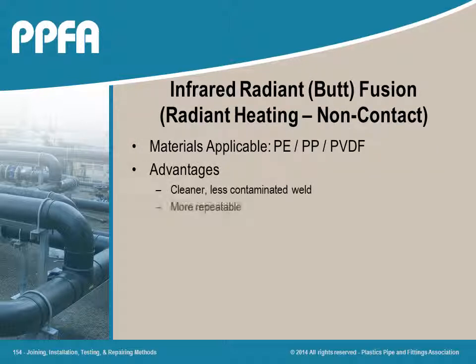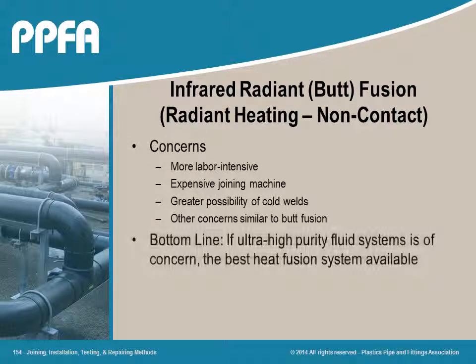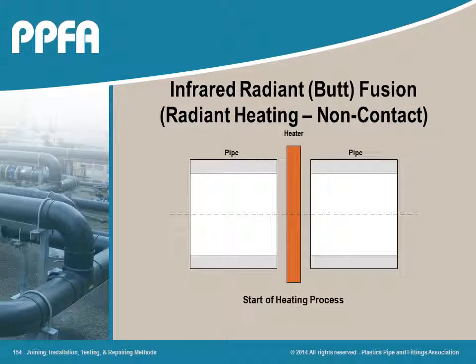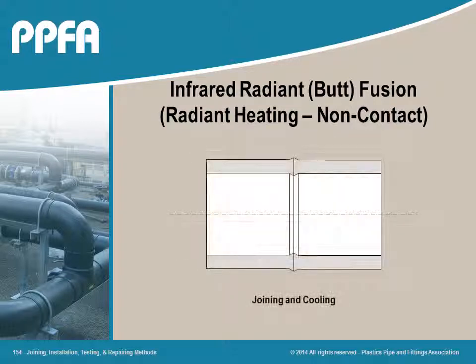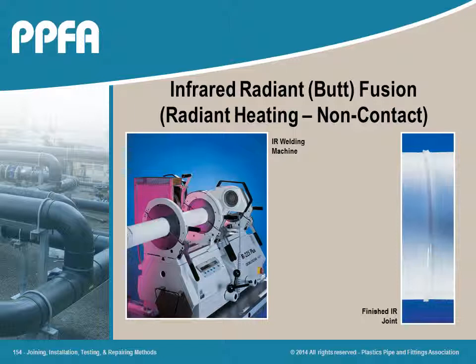Infrared radiant fusion piping joining is relatively new and used when minimum or no metal extraction or leaching can be tolerated in the fluid system. The high-tech joining method was developed primarily for the semiconductor industry in their pursuit of the highest purity water levels. The joining illustrations show that the pipe ends to be joined never come in contact with the heating element, but rather are heated by radiant heat. Once the heat source is removed, the pipe ends are brought together and held for the proper heat soak time, similar to butt fusion.